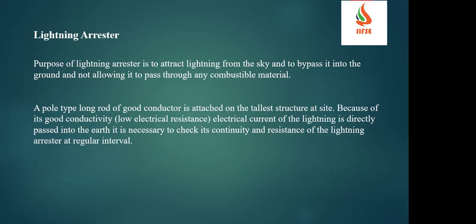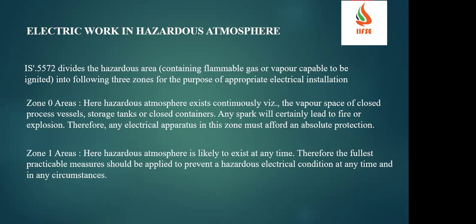Also, a pole type of long rod, a good conductor, is attached to the tallest structure. Because of its good conductivity and low electrical resistance, the electrical current of lightning is directly passed into the earth, and it is necessary to check the continuity and also the resistance of the lightning arrestor at regular intervals. It is a low resistance conductor, and the resistance of the earth pit is also maintained so low that any lightning which is attracted has to come directly to the earth.